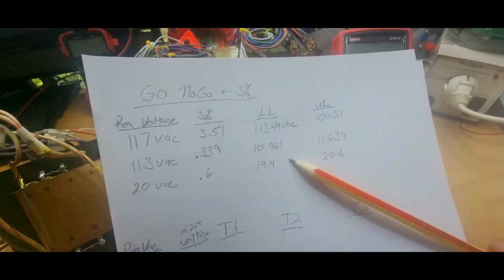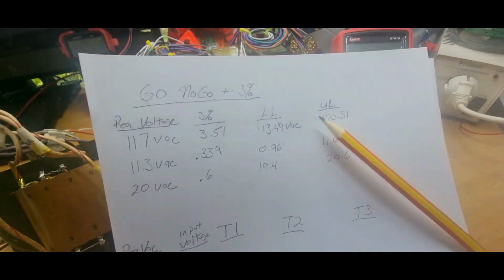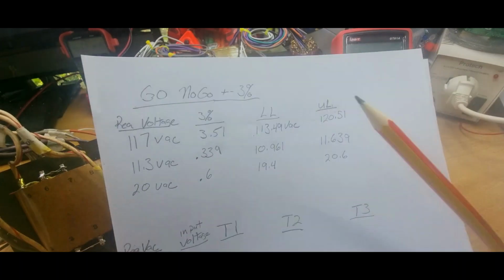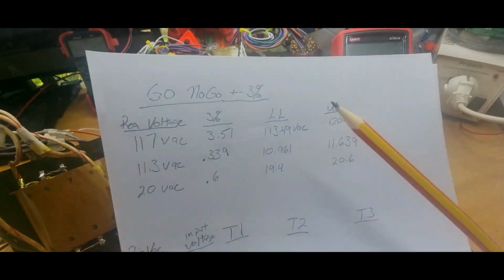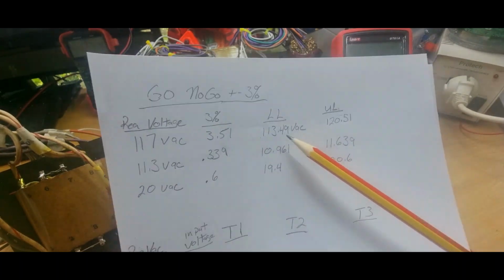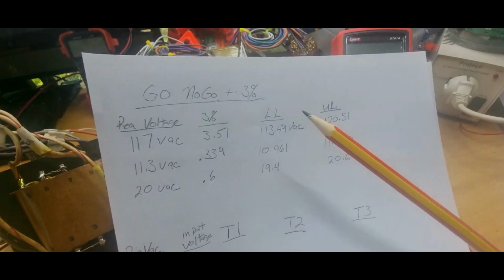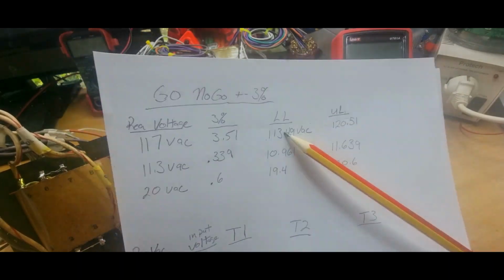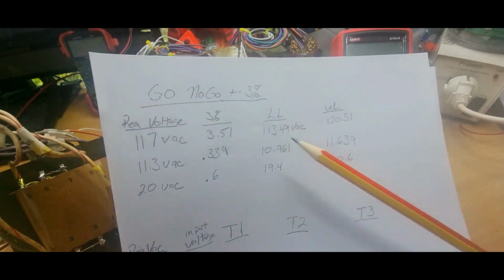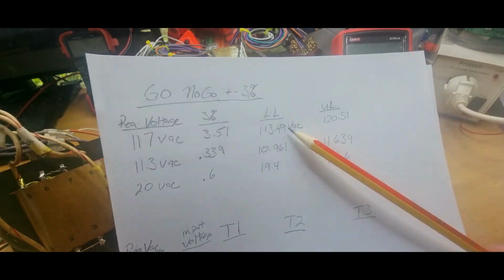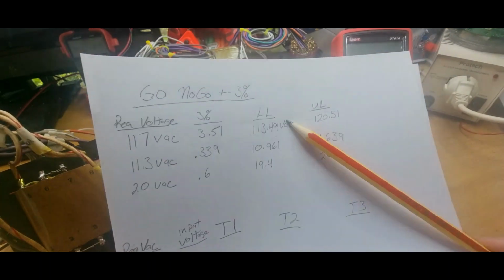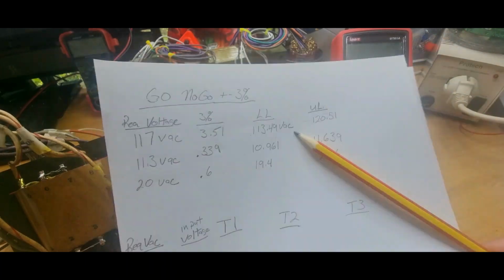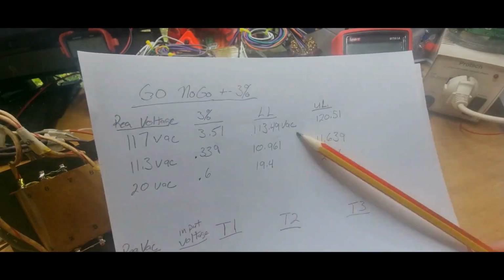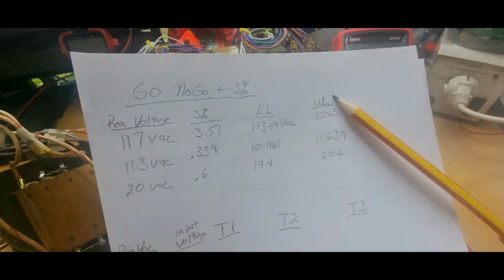Another big thing to keep in mind: we're testing these transformers with no load, so the actual tested voltage won't be exactly where it's engineered to be. I don't have a proper load, so I'll just see where they land and let my power supply act as the load when we get close.